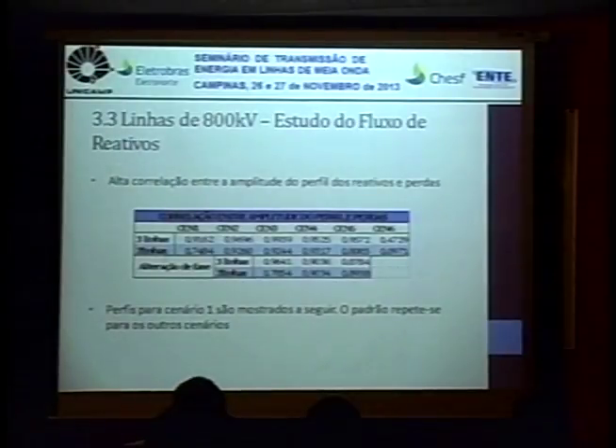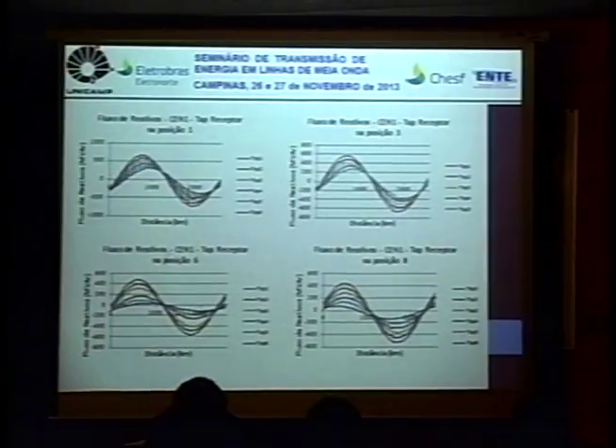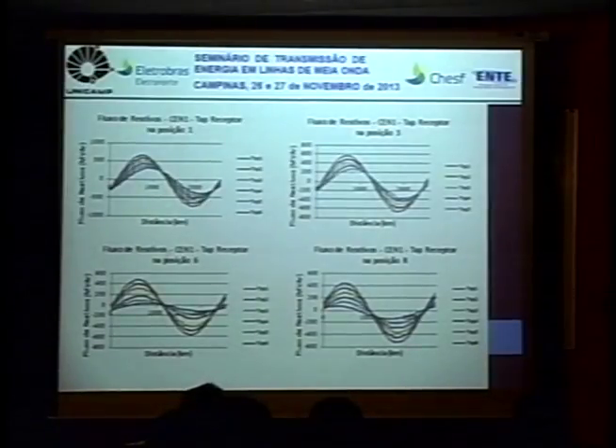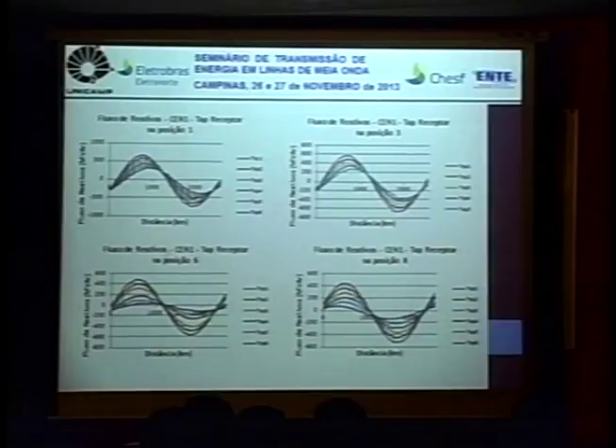I have already talked about this. I'm going to show you the results directly. So this is the reactive power flow in the line. By making this adjustment and changing the tap in both positions, here the tap is fixed in the receiving terminal. I'm varying the tap in the emission terminal.